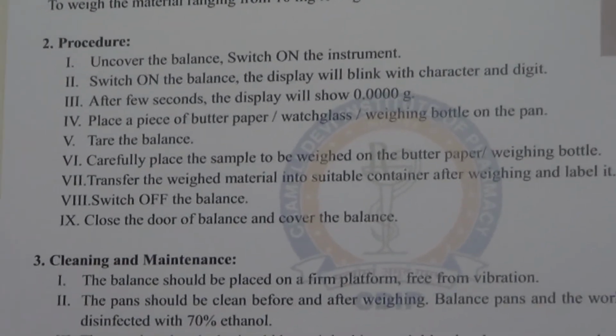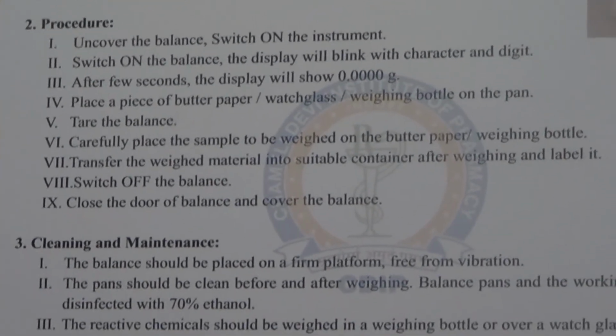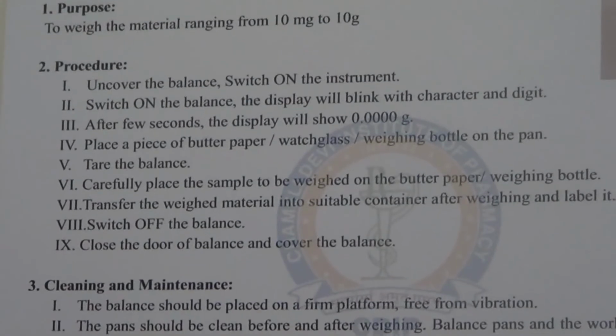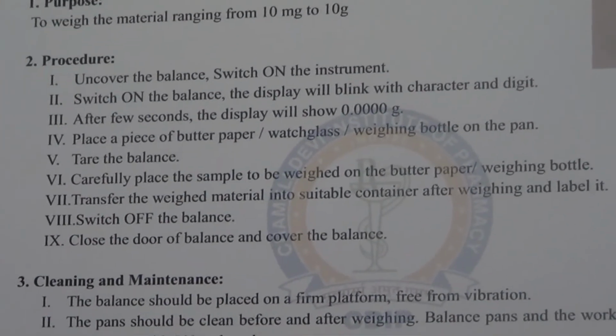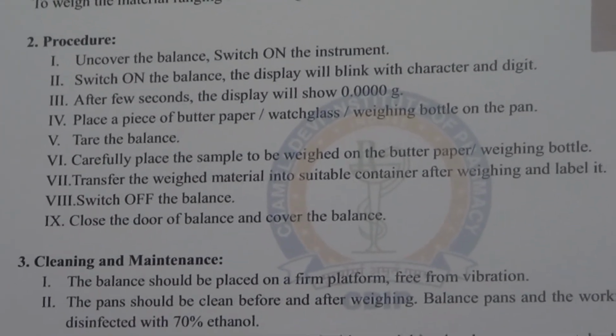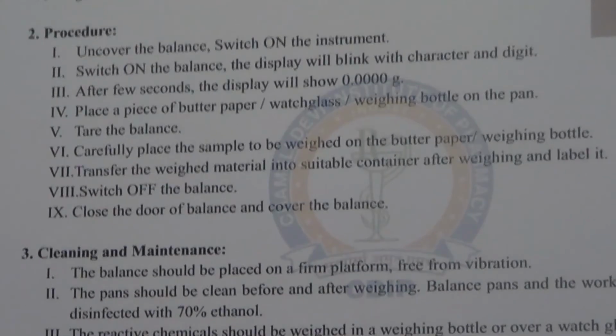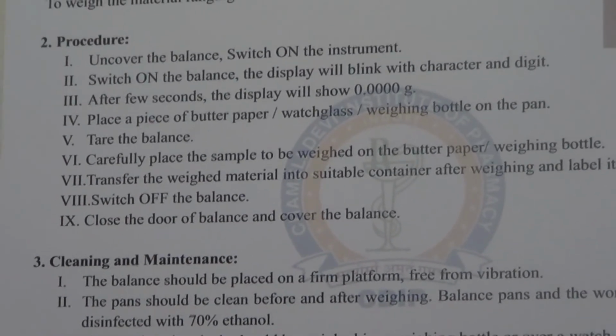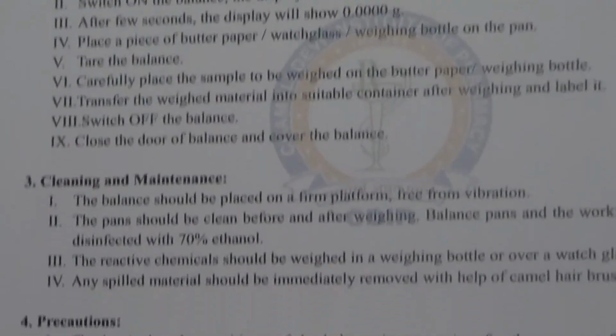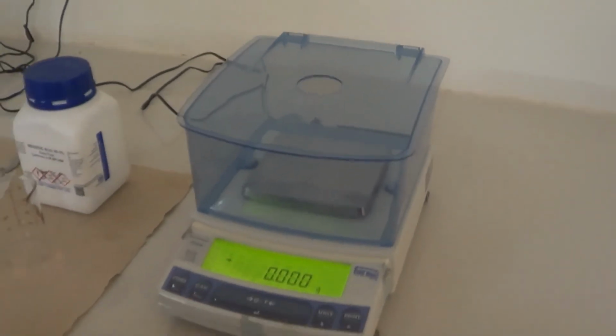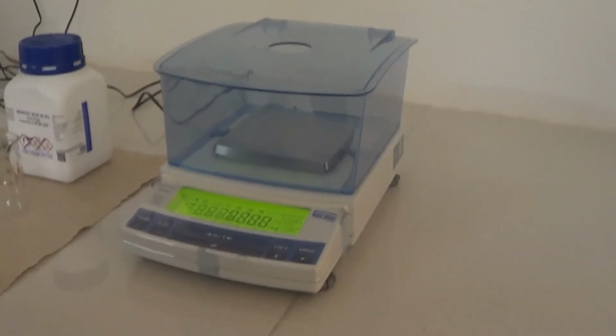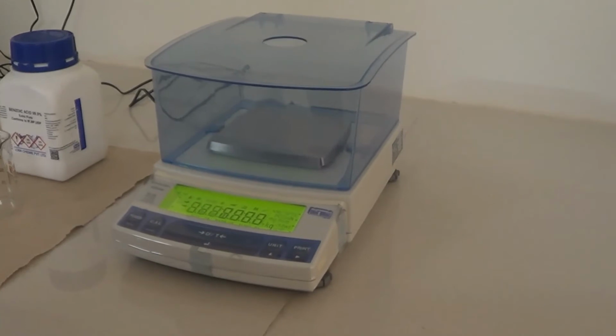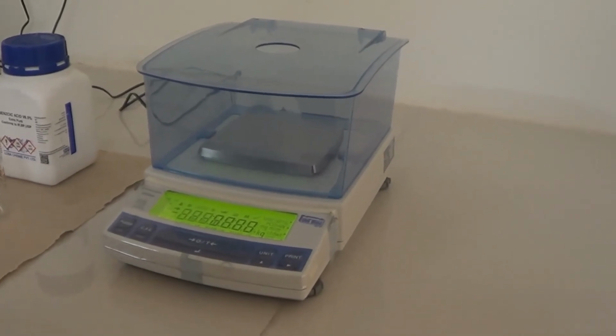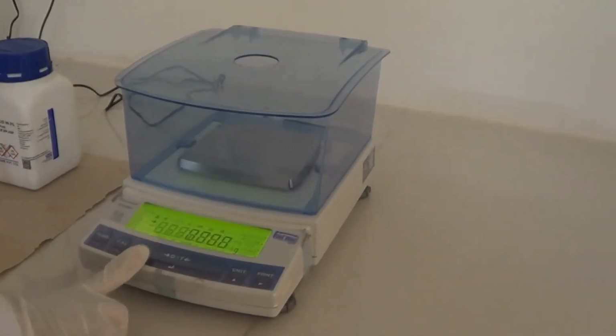Now moving to the working of this balance. Balances do not directly measure mass. They measure the force that acts downwards on the balance pan. Most weighing balances are electromagnetic balances, but here in this model, the electromagnet is replaced by a block made up of aluminium alloy, which is connected with some electrical system. The electric current required to generate this force is proportional to the weight and so can be used with appropriate calibration. This weight is displayed onto the screen.